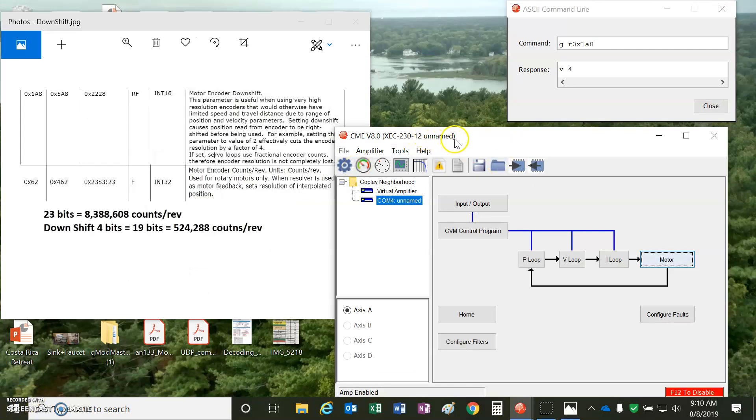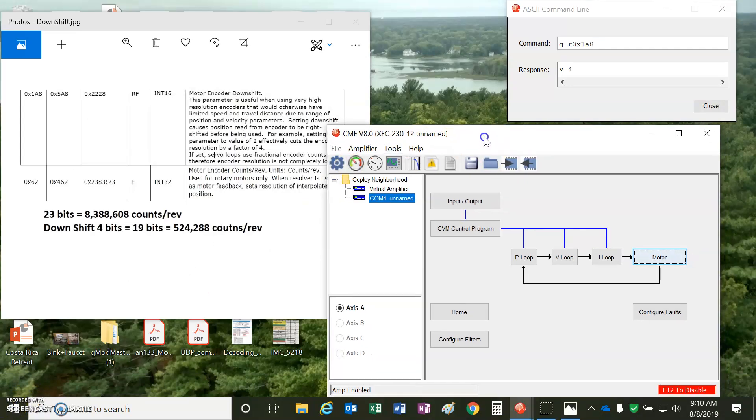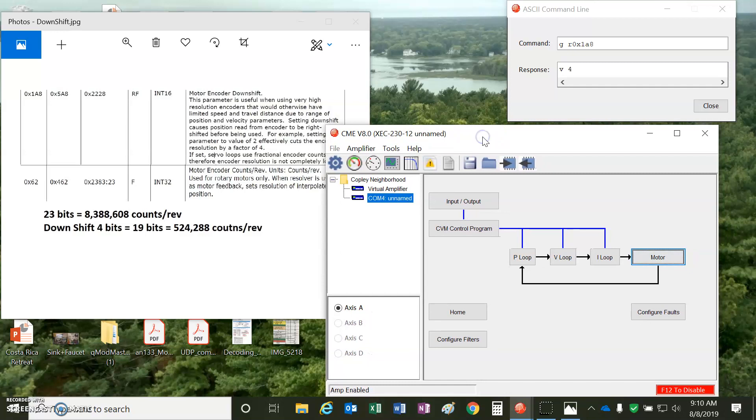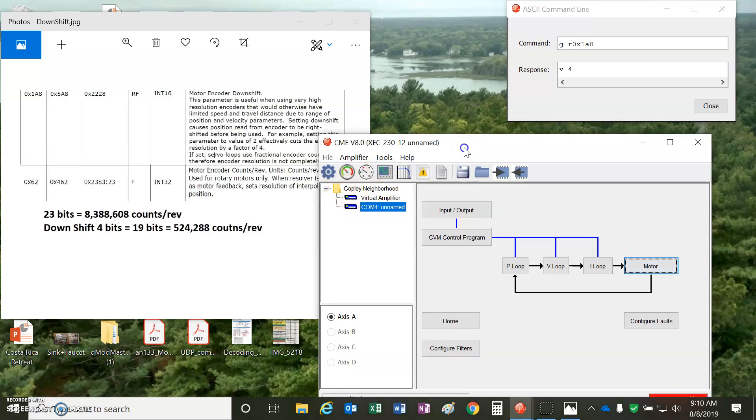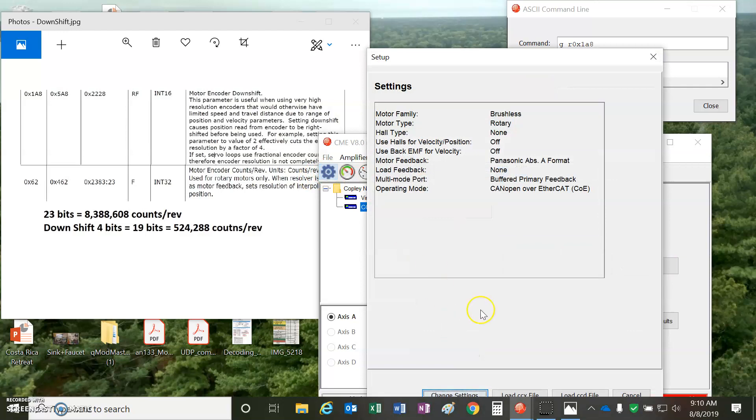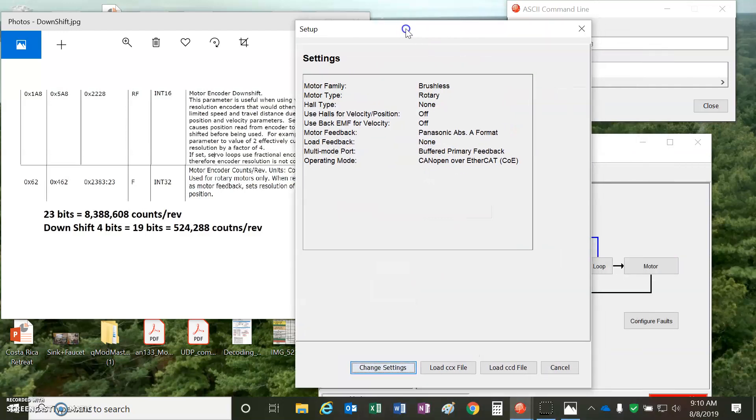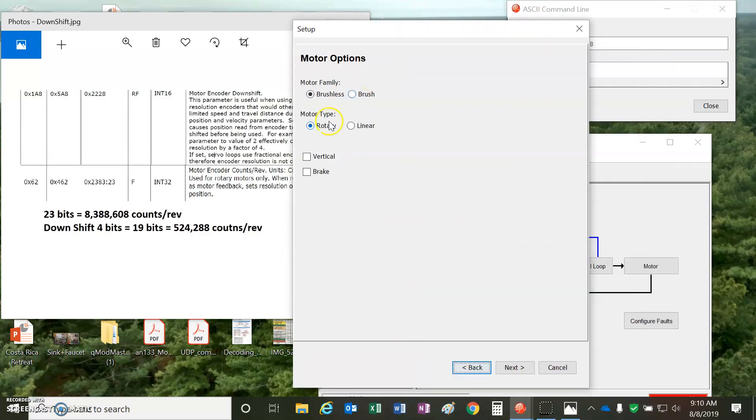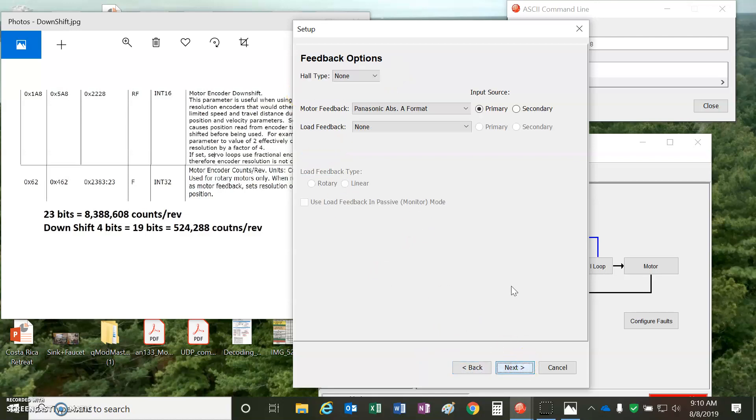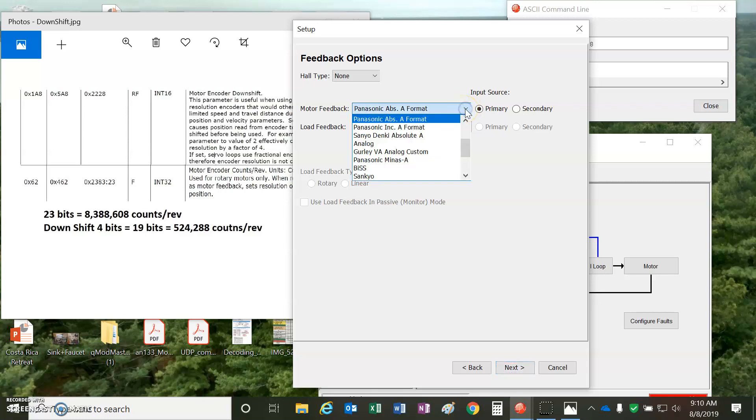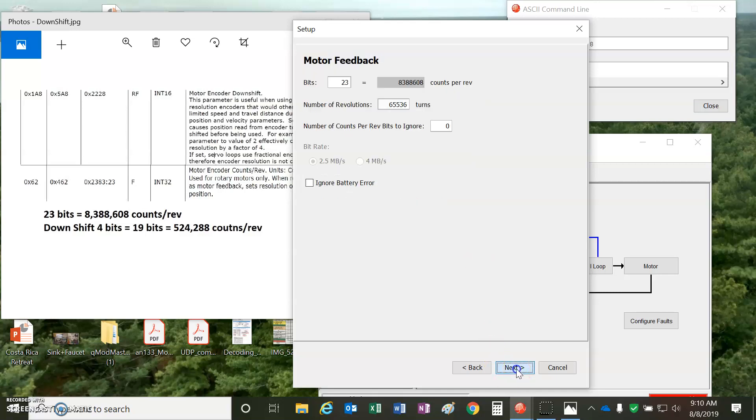So, I connected CME version 8.0 using a SER-USB-RJ11 Copley USB to serial adapter. And in the beginning, we do the setup for this motor. We'll enter the information about the motor. This one's brushless rotary with no brake. It's a Panasonic Absolute A, so we can pick that from the list. If it was an incremental A, that would be an option, too. And this is a 23-bit with 65536 turns. There's no ignore bits on this one. We could ignore the battery, but I've got a battery here today, so I'm going to use it.